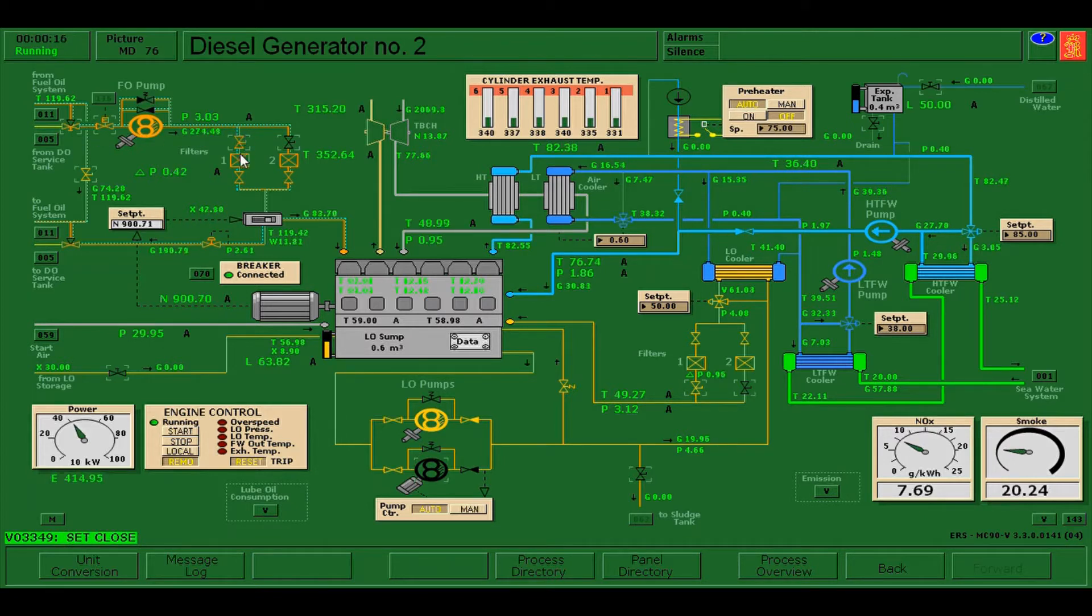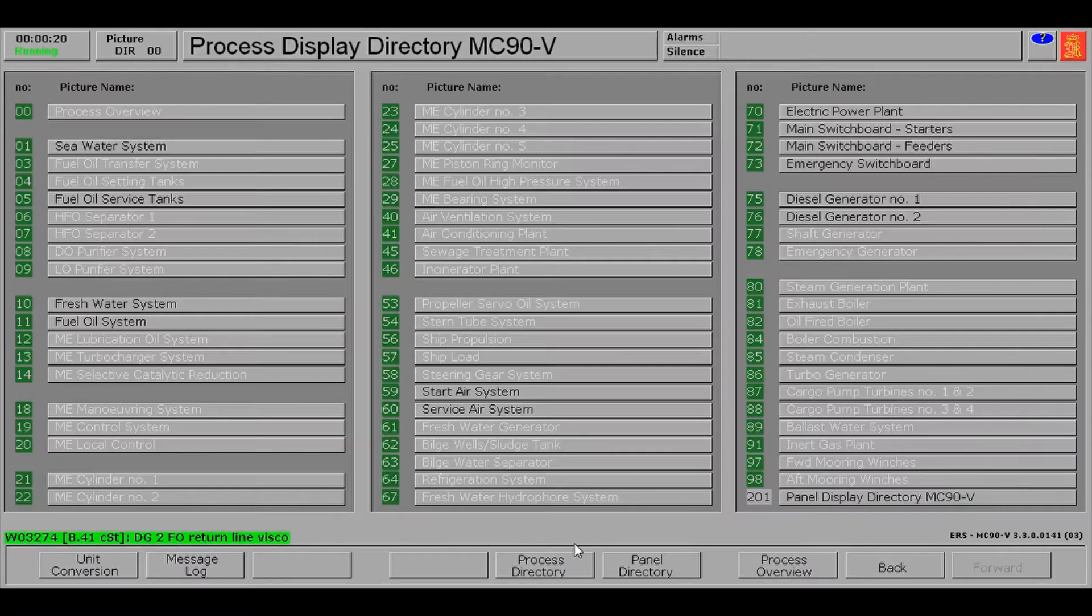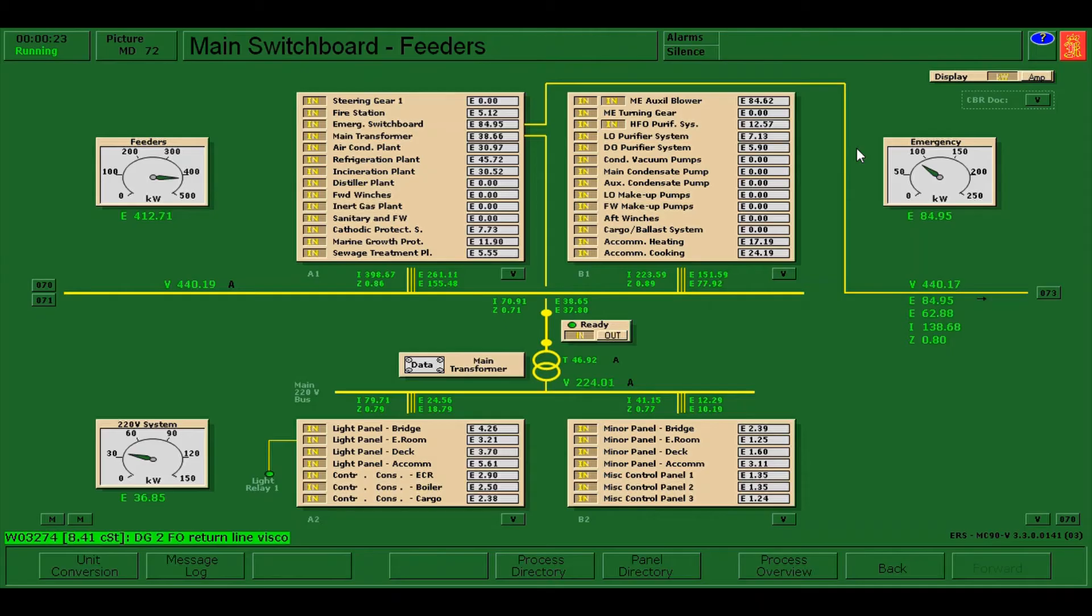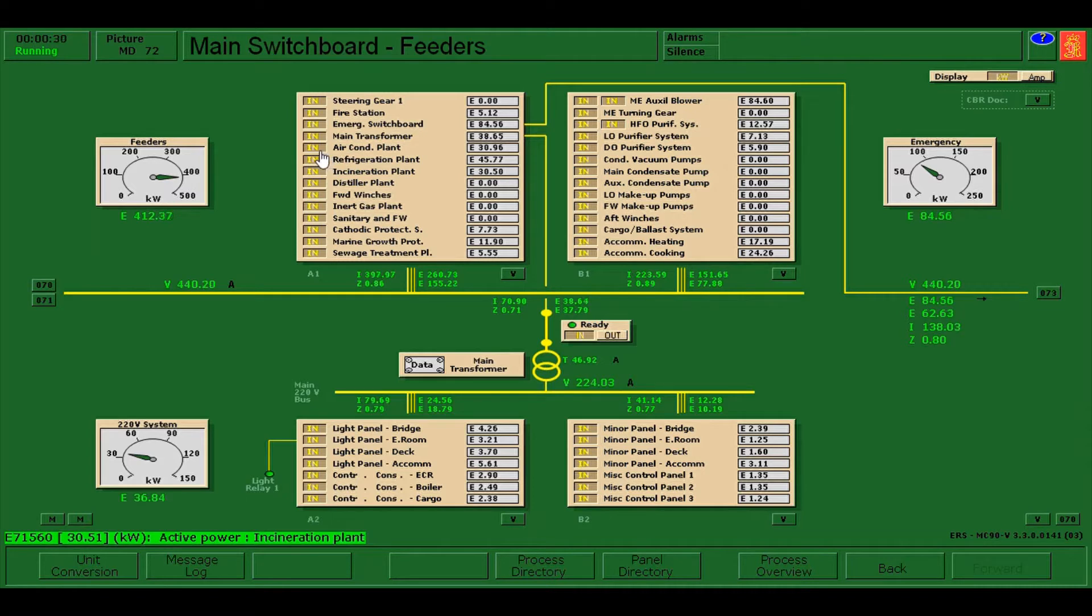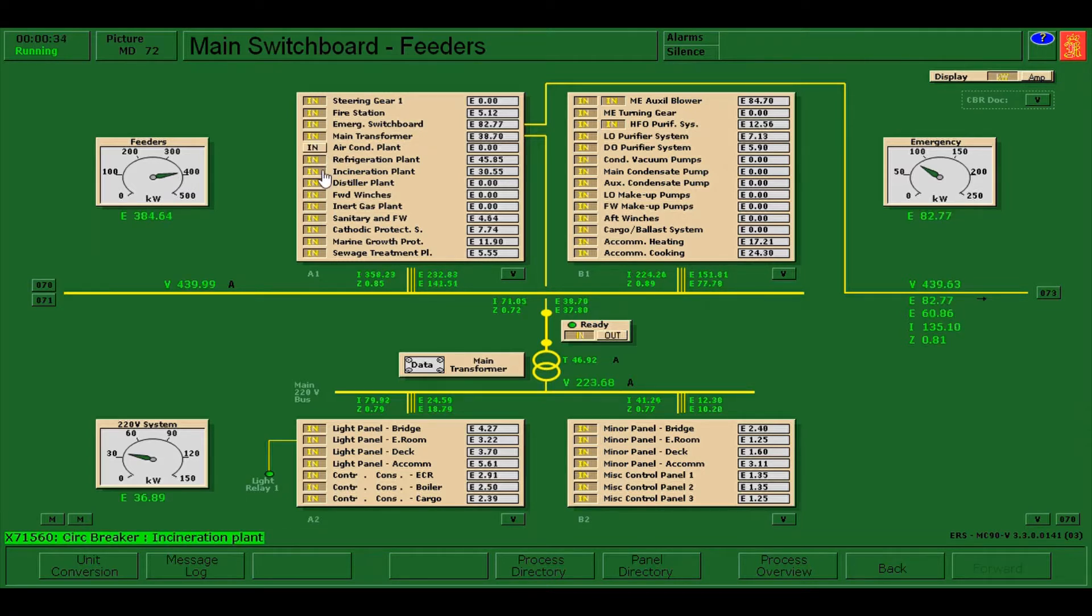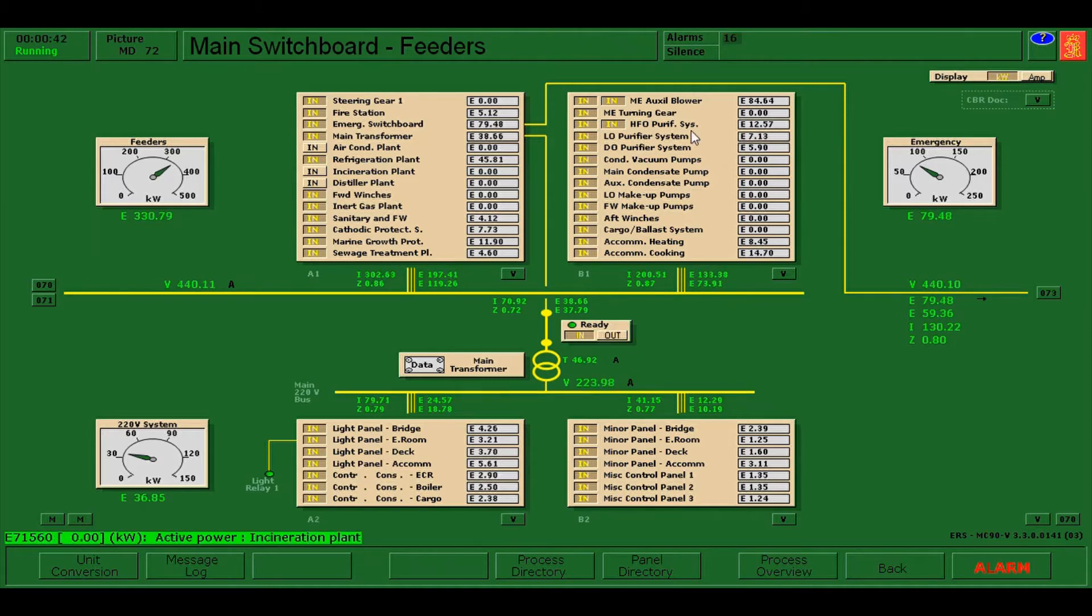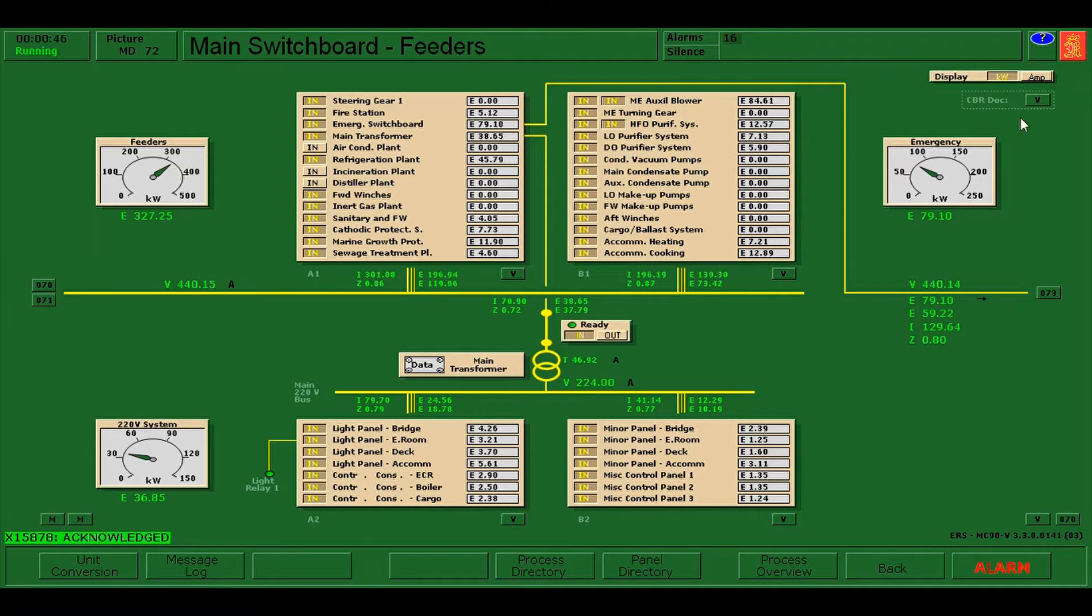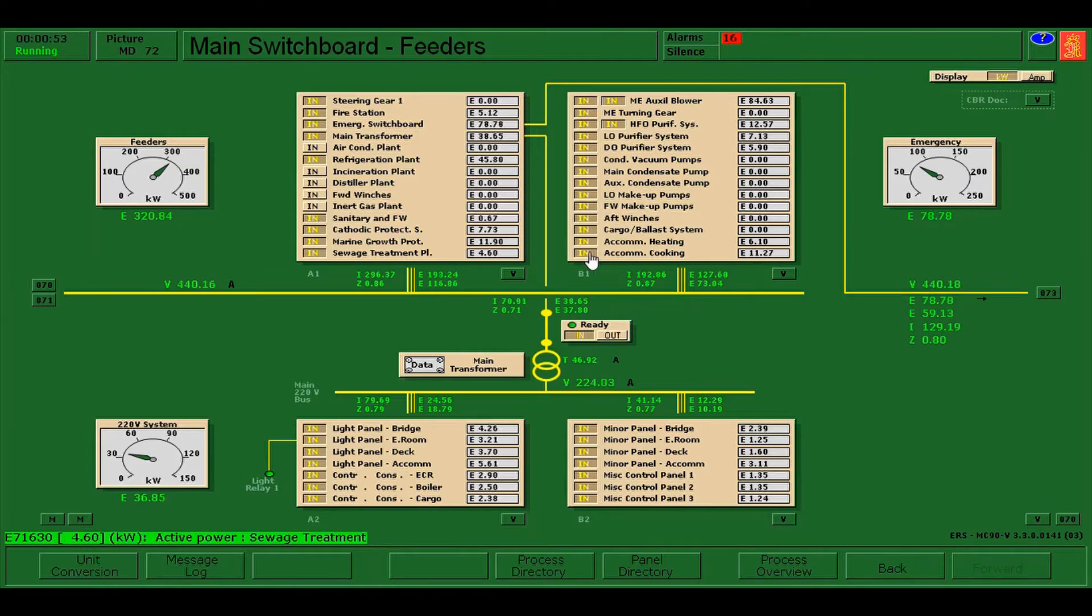While flushing, we can go to the main switchboard feeders and try to disconnect the less essential load so that we will not have a preferential trip. I will disconnect air-condition and incineration plant, distiller plant. There is an alarm, press shift F12 to silent and click this button, click the blinking alert.